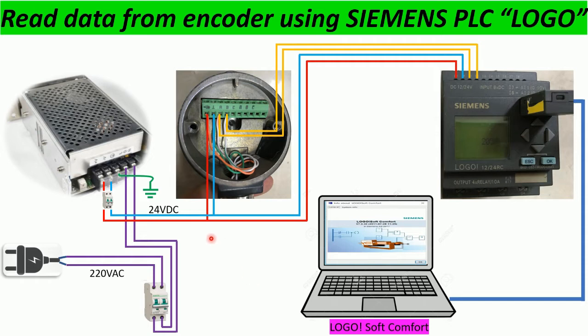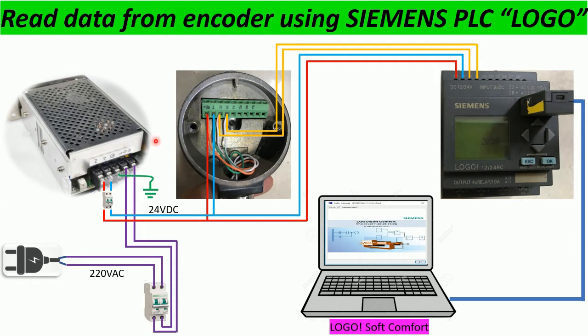First, I have a power plug at 220 volt AC connected to a circuit breaker and supply to a power supply. For this power supply, the input is 220 volt AC and the output is 24 volt DC. Here is the connection from the power supply to the PLC Siemens Logo at 24 volt DC. For the encoder, we supply 24 volt DC, and this is the signal from the encoder to the input of the PLC Logo.